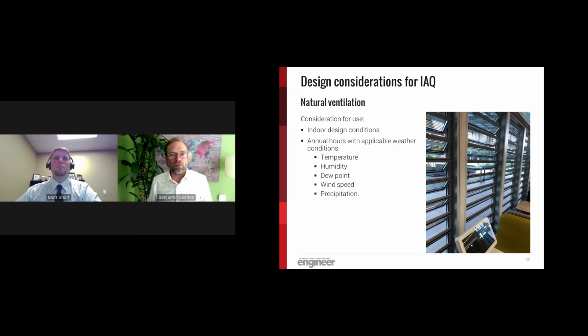A lot of people don't like having automated natural ventilation systems on their building because if something doesn't happen right and it introduces the wrong conditions of the air, you might get condensation on flooring surfaces and create a dangerous environment. But it can be done effectively. You just want to make sure that you look at these parts in the application and that it's tested and works well. Some people only want to see this when occupied, and there are some climate zones where you can't really effectively design natural ventilation because of the outdoor temperatures. It'll never provide the conditioning that you want to have inside your building.